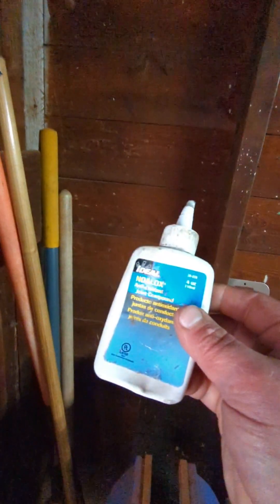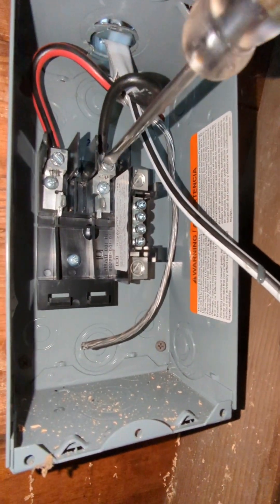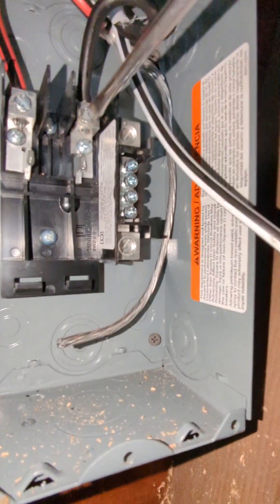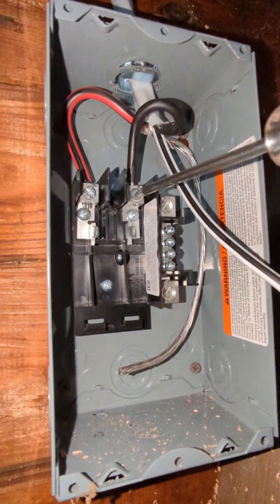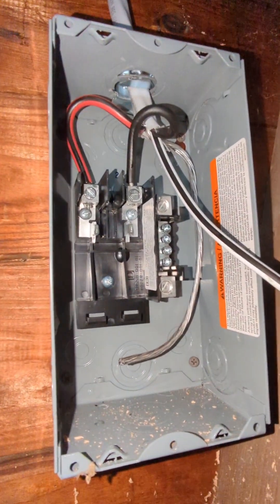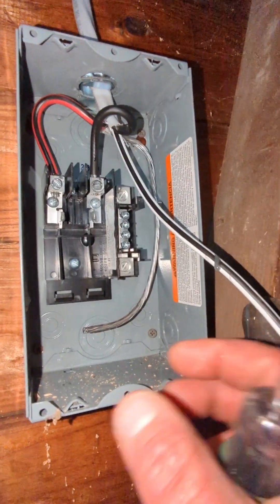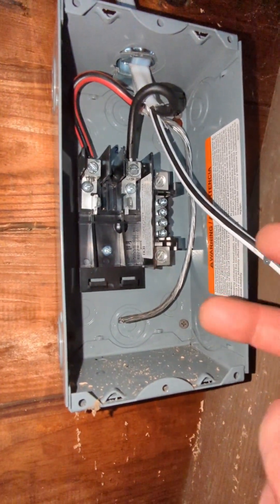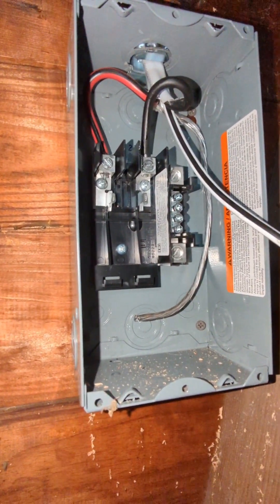Noalox is antioxidant compound specifically formulated for aluminum — I'm sure there are other brands, this is what I grabbed from the big box store. I'm cranking these connections down and then coming back in a few minutes to retighten them. The advantage here is it's super cold right now — the aluminum has already shrunk to about the smallest it's going to get inside that connection.